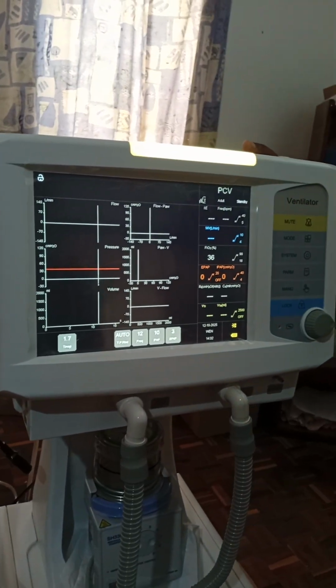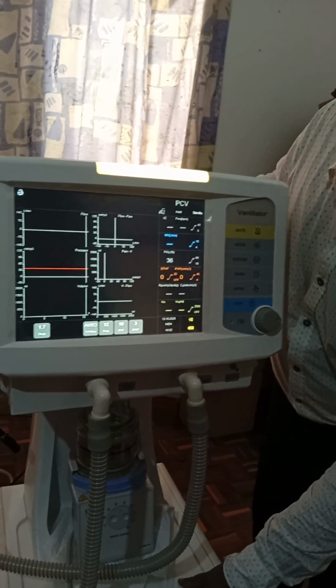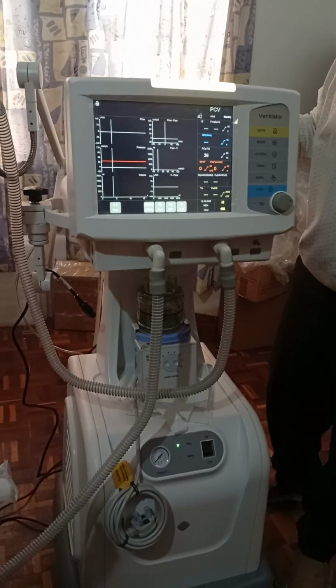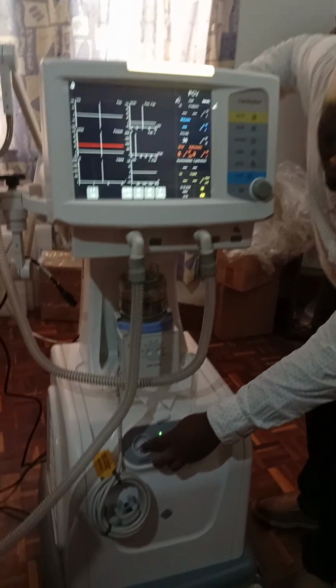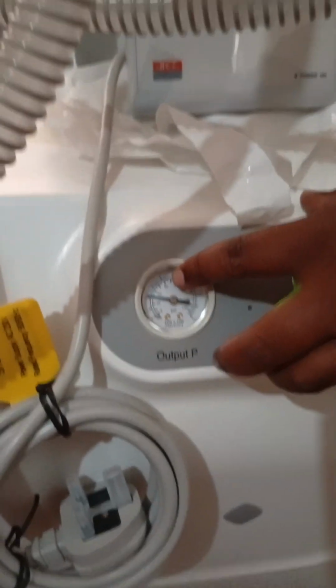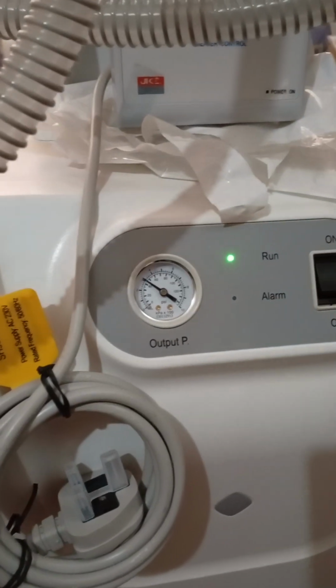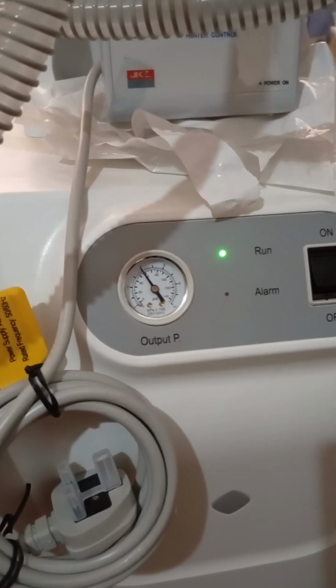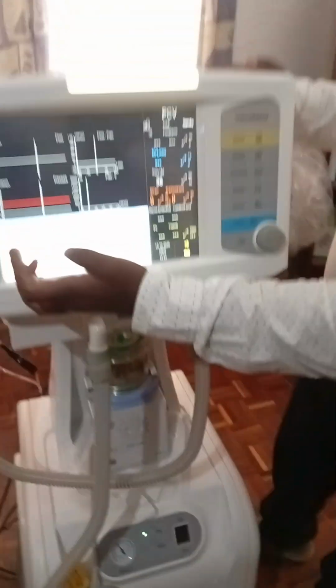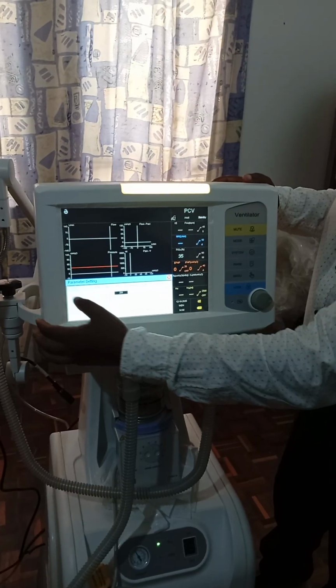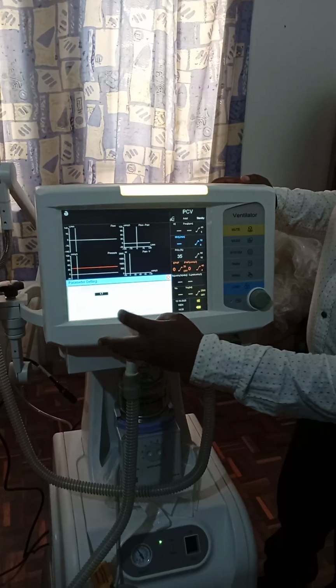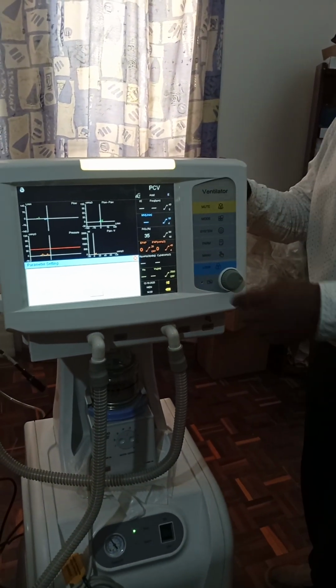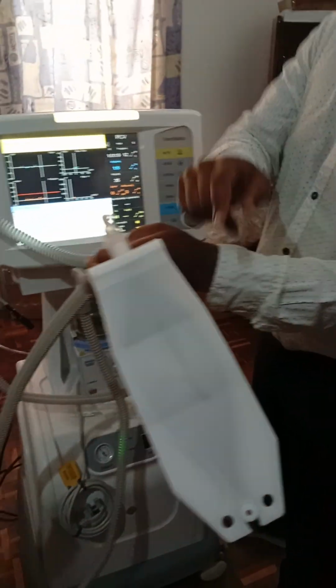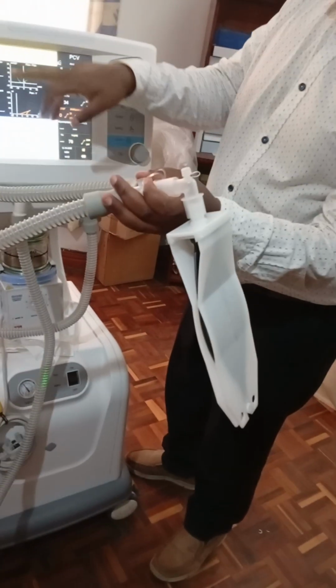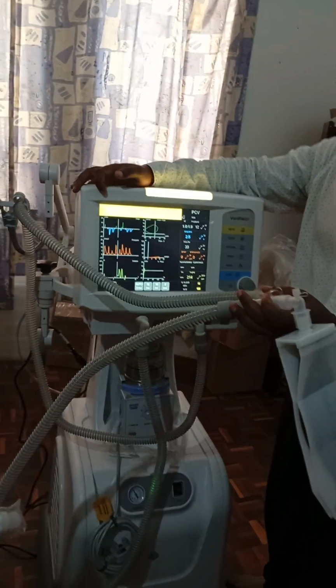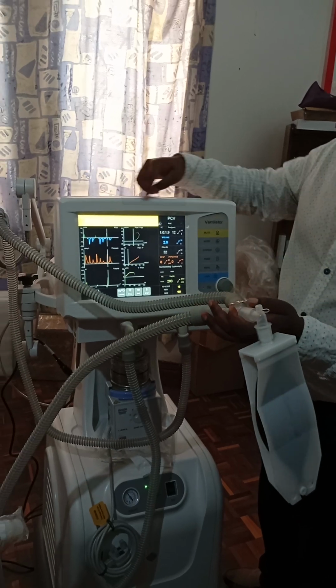Now for this case, we can try using the compressor, the medical air. When you switch on the medical air, this gauge should rise up to 4 bar here. It will stop at 4, and then that pressure is already announced. Now if you select the parameter, you'll see the several parameters you have. Assuming you select this one, you can adjust these parameters and confirm. Once you confirm, you can see our test plan is already ready. You are now on ventilation mode, and you can see the graph. The machine also gives you both the visual alarm and the audio alarm, and also the lighting.